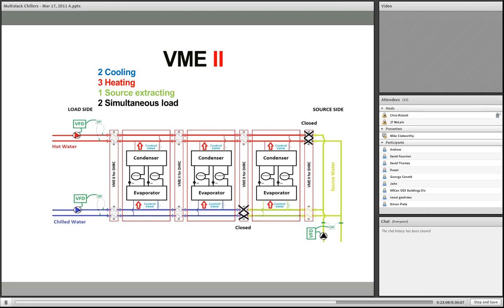And then this one is just another variation, 2 in cooling but 3 in heating. And as you can see, with 3 in heating, I've got this set of valves closed. All the heat that's being rejected is going to the hot water load, but I don't need quite as much chilled water, so I've got that set of valves closed. So I've got 2 modules on the chilled load, and then for this 3rd module that I'm needing heat, I'm getting it from the source sink down here. Now, if you've been thinking about this design while I've been talking, one of the things that you may have seen is that all the fluid is commingled.